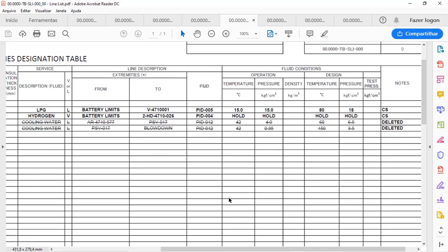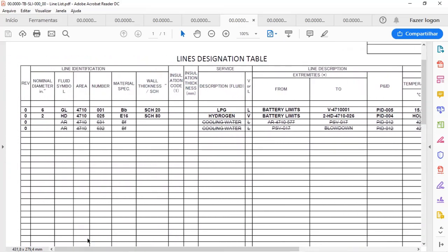Usually, companies have a handbook with piping specifications that is identified in the line identification. So here, for instance, this line identification, line numbering, is the nominal diameter, fluid symbol, area, number, and material spec. This material spec, if you see the material spec handbook, is related to a set of materials that already has the maximum allowable pressure associated with it, and the design temperature also for this material.